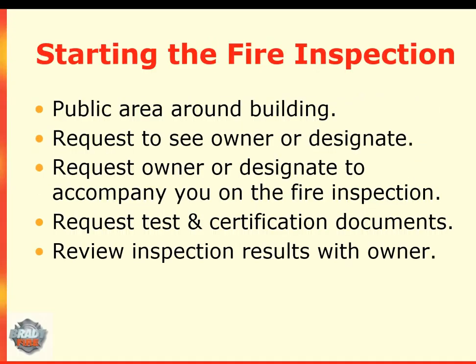It's a good idea to begin on the outside of the building. Initial observations from outside may include the street address, the main entrance, fire department connections, utility locations, and the nearest hydrant, exposed buildings, and the general condition of the building and the surrounding grounds. Be patient waiting for the owner, especially during cold calls.